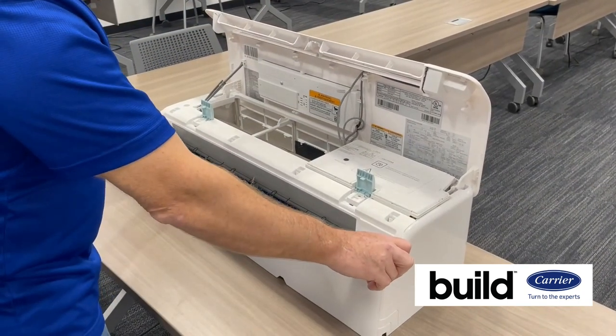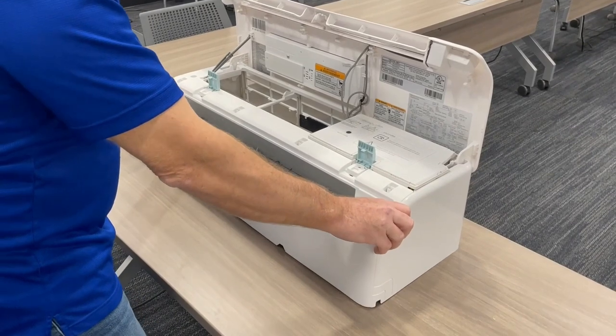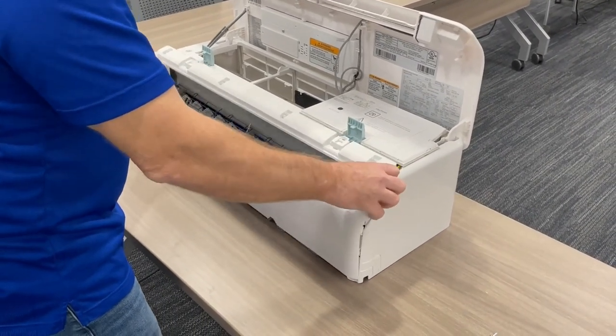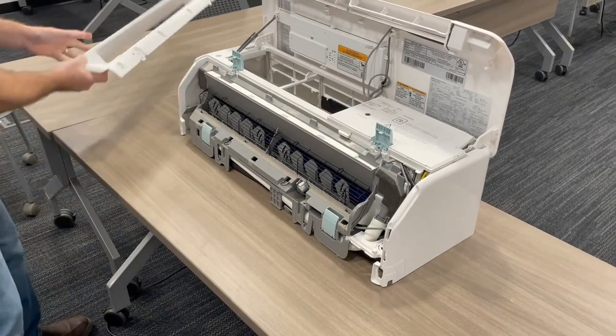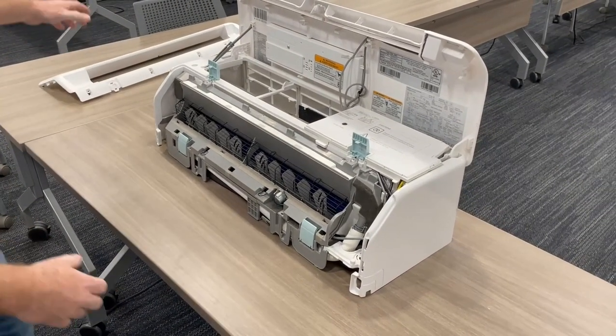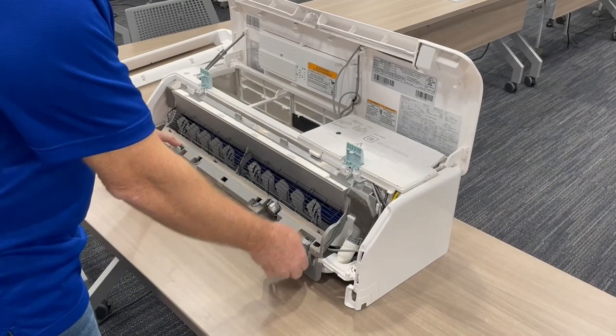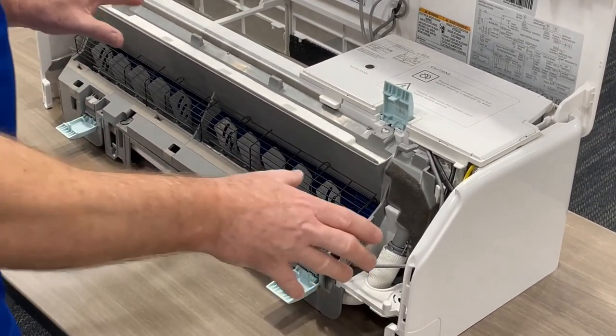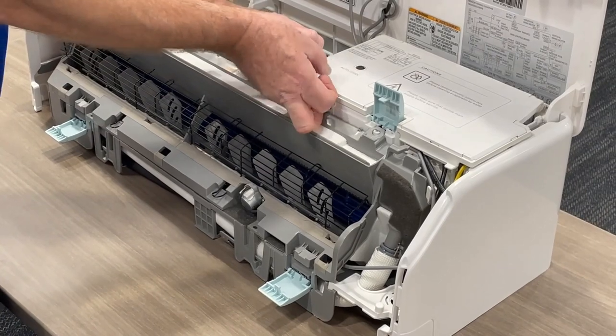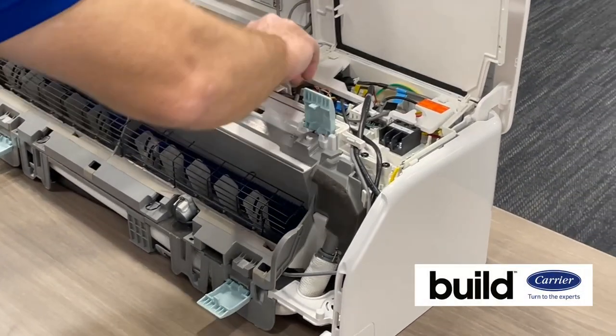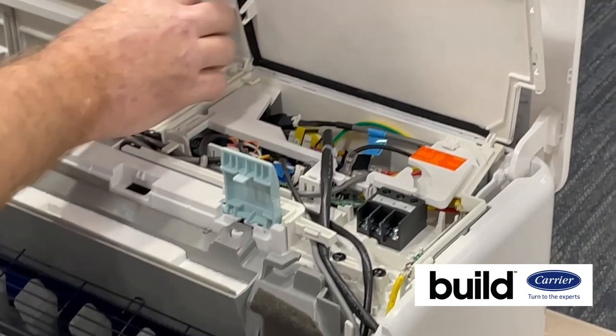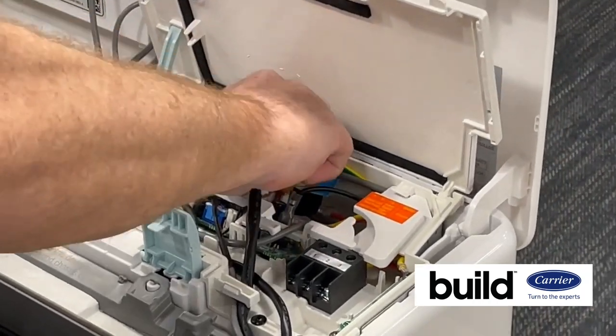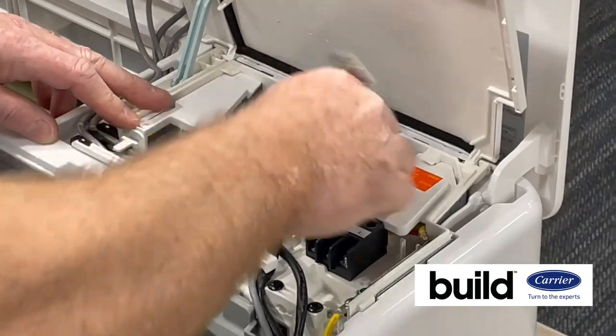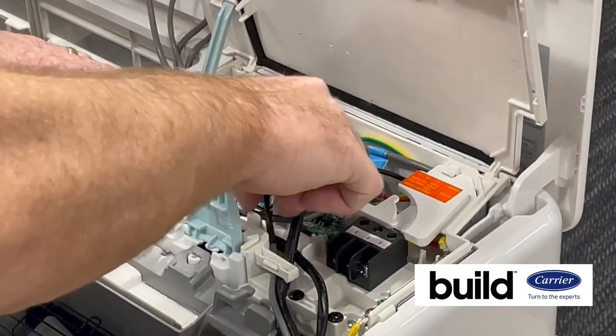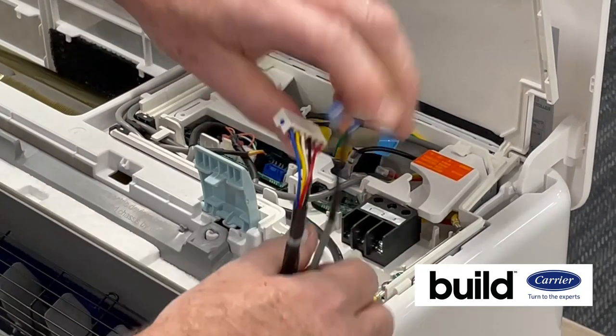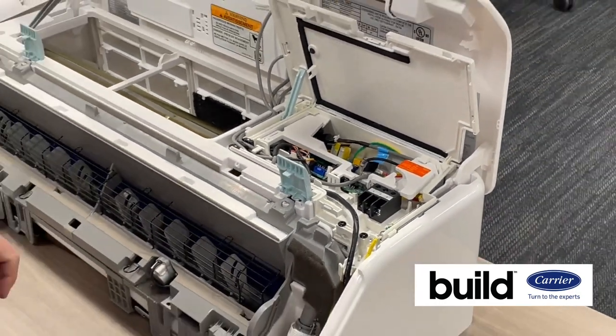Then right here and right here, you'll see there are handles that tell you to pull up. When you pull up, this whole bottom piece comes out, and then you'll see two more clasps, right here and right here - take those loose. Before you do anything else, you need to take your electrical panel and prop that up, you've got a little prop rod right here. Because your blower motor harness right here, and your louver motor harness right here, need to be disconnected in order for you to pull the blower out.